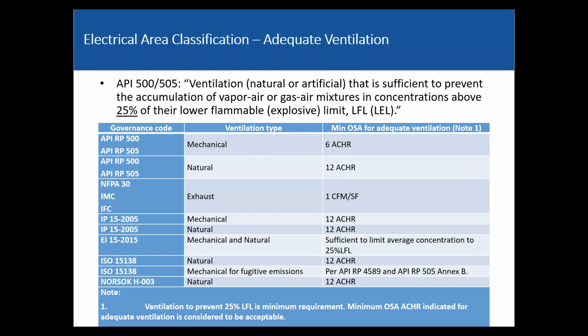LEL is your lower explosive limit. It's interchangeable with LFL, which is lower flammable limit. They're not quite the same, but they're used interchangeably. So for adequate ventilation, API 500 and 505 say provide this. Many documents will talk about that, and you're like, what is adequate ventilation?